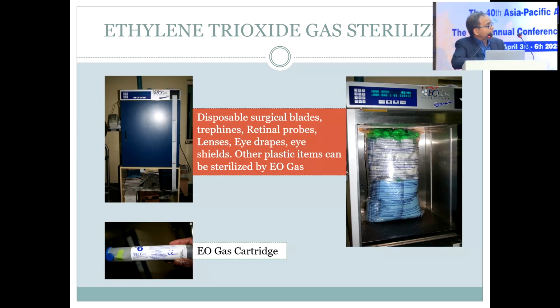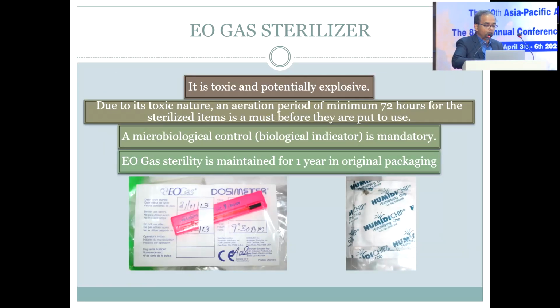This is the EO gas sterilizer that is placed in it along with a dosimeter that identifies whether the sterilization has been done properly. It's important to remember that EO gas is toxic and potentially explosive, and due to its toxic nature, do not use these instruments immediately. They should be used after an aeration period of minimum 72 hours. A microbiological control is mandatory, and EO gas sterility can be maintained for 1 year if packed properly in the original packing.